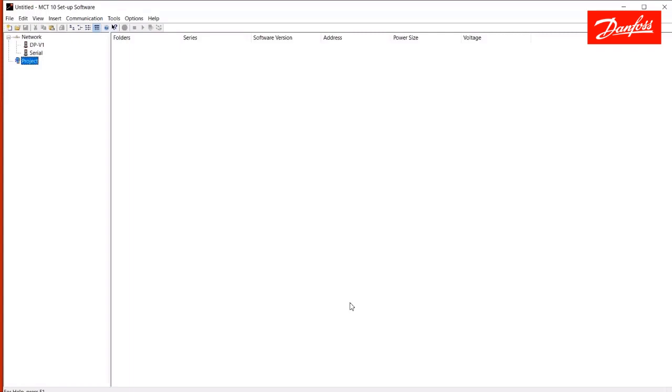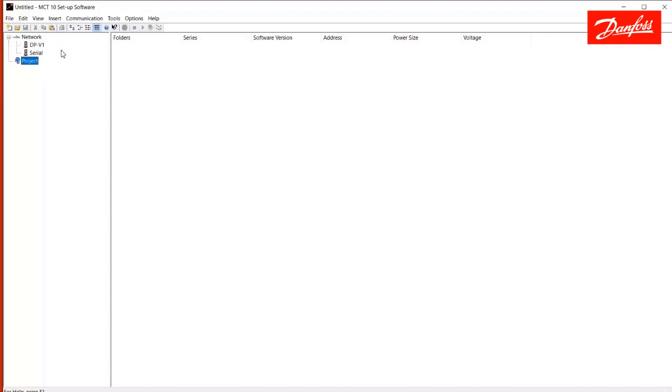Here we see the first screen or the opening screen of MCT10. We have two sides here. We have the network side and the project side. Anything that appears in the network tree, there's a live connection between the computer running the MCT10 and a VFD. On the project side, the drives that would be on the project side are offline. That's where you can save project files to, in the project side where I can access them later.